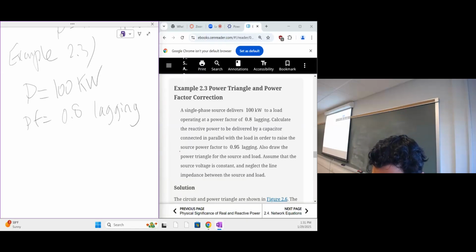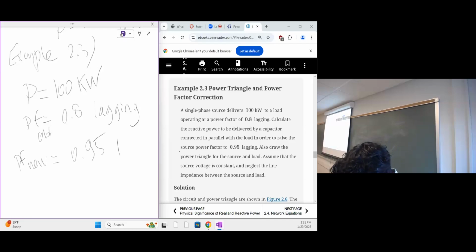So let's say the old power factor is this value, and the new power factor should be 0.95 lagging. First, we need to calculate our old Q. We have P and some power factor, and then we see what we should do to raise that power factor to 0.95.